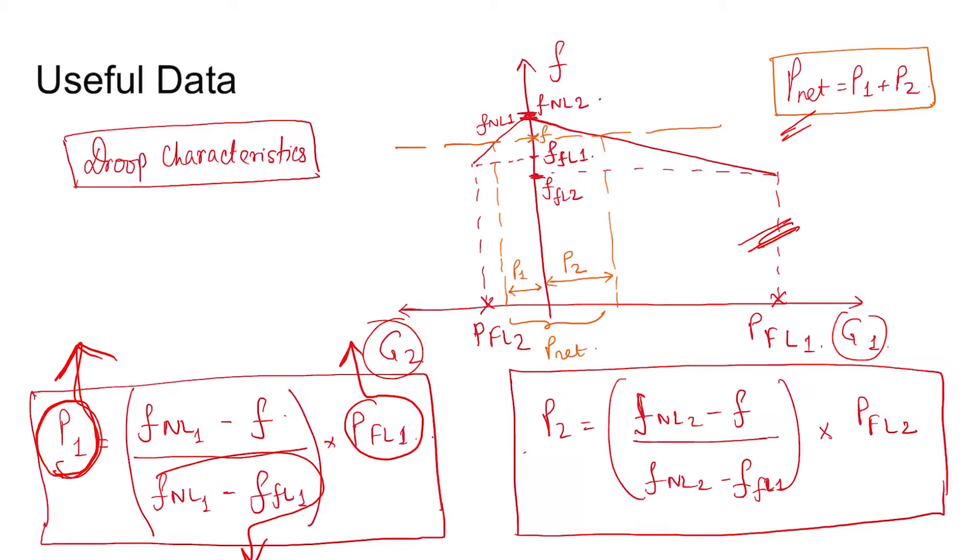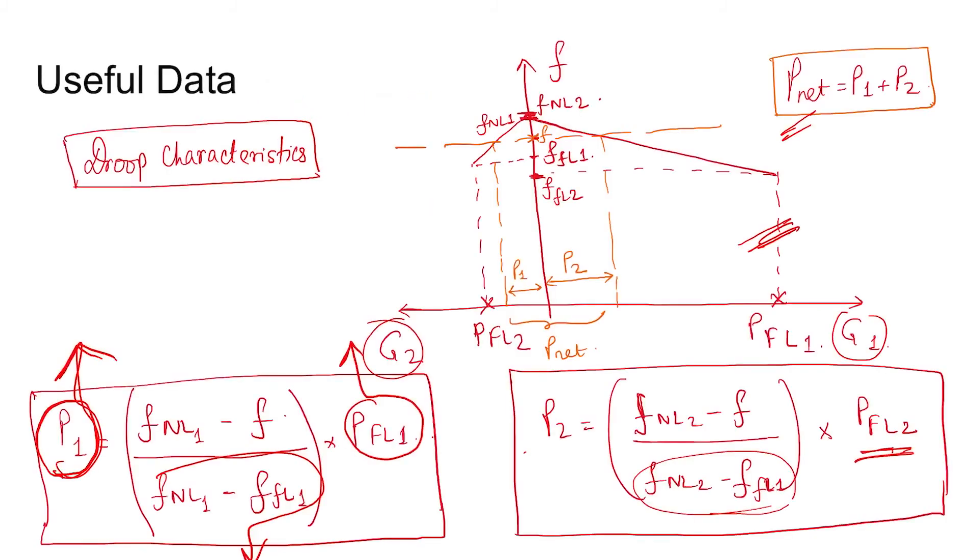P2 is no load frequency two minus the final frequency divided by no load minus full load frequency into capacity, full load capacity of generator two. P_net is specified as 500 megawatts.